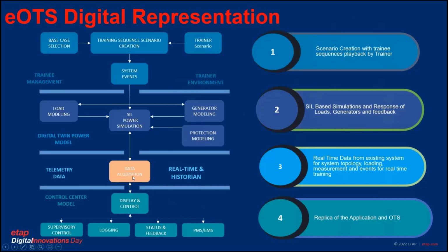ETAP essentially comes along with a software-in-the-loop power simulation environment, where we create a digital twin power model. That digital twin has representations of your source generator modeling, load modeling, and all the protection and metering modeling, which connects to the data acquisition layer of these supervisory control systems, taking real-time data and system events into an OTS environment.